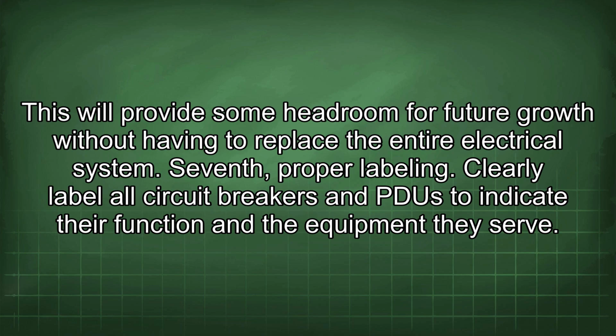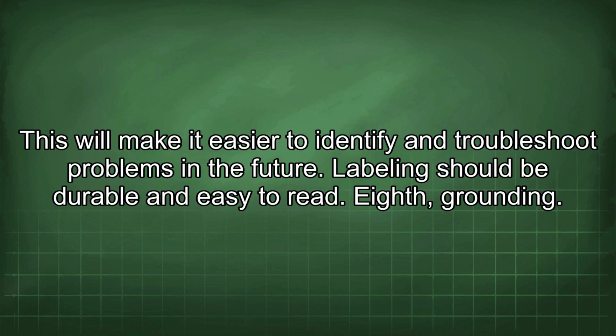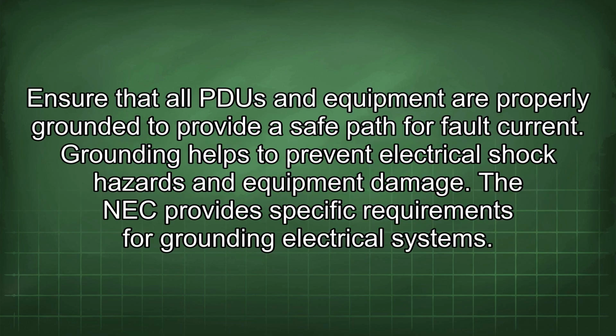Clearly label all circuit breakers and PDU to indicate their function and the equipment they serve. This will make it easier to identify and troubleshoot problems in the future. Labeling should be durable and easy to read. Eighth, grounding. Ensure that all PDU and equipment are properly grounded to provide a safe path for fault current.